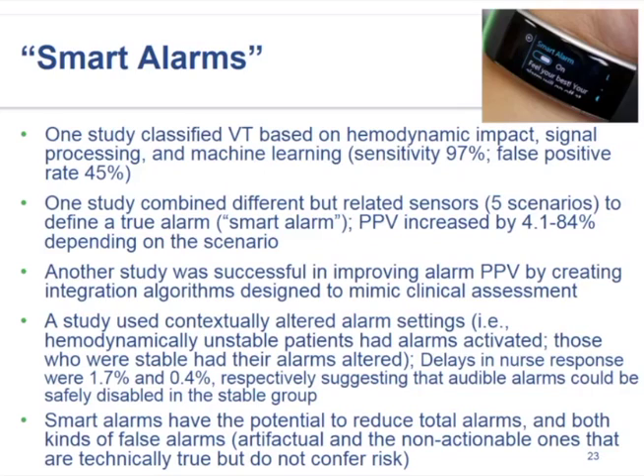Other studies were successful in improving alarm PPV by creating integrated algorithms designed to mimic how physicians and nurses make a clinical assessment of a patient. And contextuality is another area that has much promise. One study used contextually altered alarm settings based on whether a patient was known to be hemodynamically unstable or not. Under those circumstances, they were able to either deliberately suppress or keep the alarms activated, and found that delays in nurse response were 1.7 and 0.4% respectively, suggesting that such a strategy of reducing audible alarms could be safely performed in the patient group that was considered hemodynamically stable.